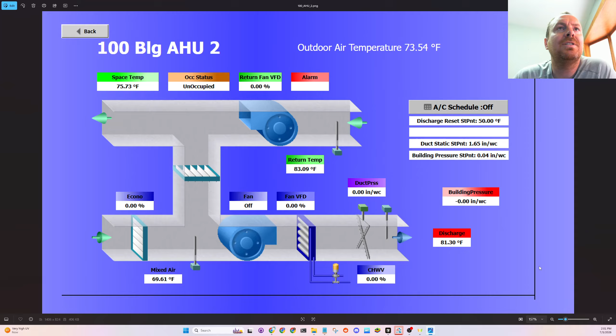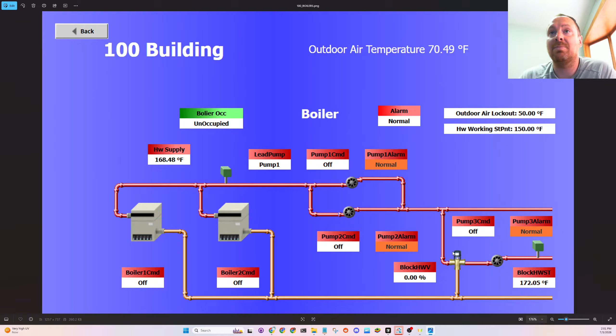Boiler system. The building must be old enough that it's not even a variable pumping system. And then there's a mixing valve for the hot water supply set point. And then the chiller plant just looks to me like 2 air-cooled chillers and an outside air enable set point of 55. So to me, this is a red flag right here, is that we can technically be free cooling on the air handling unit systems for sure at 55 degrees Fahrenheit.